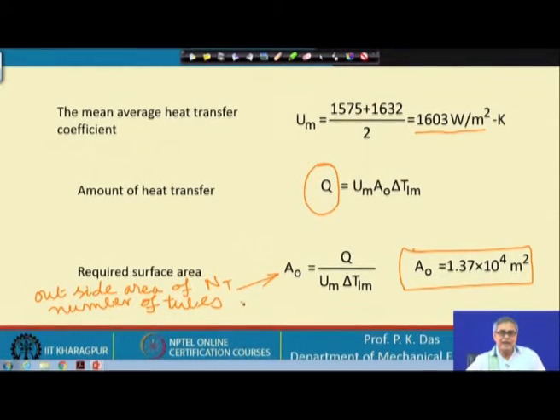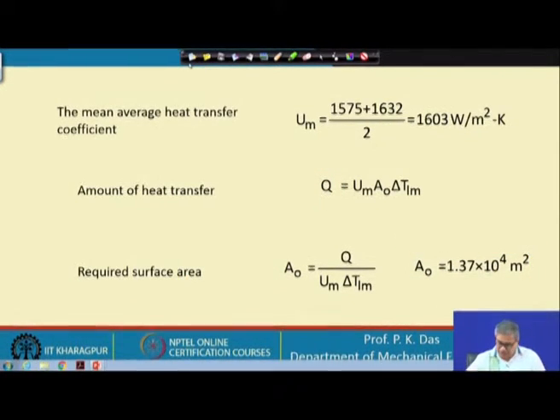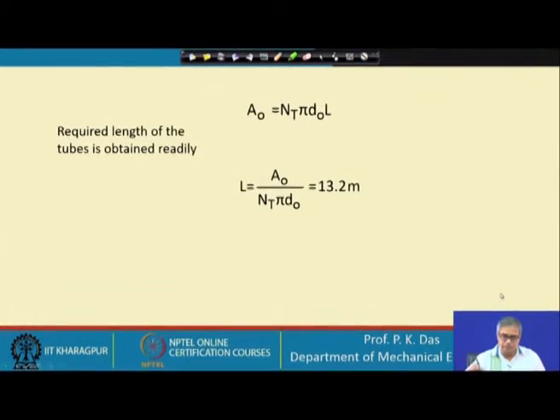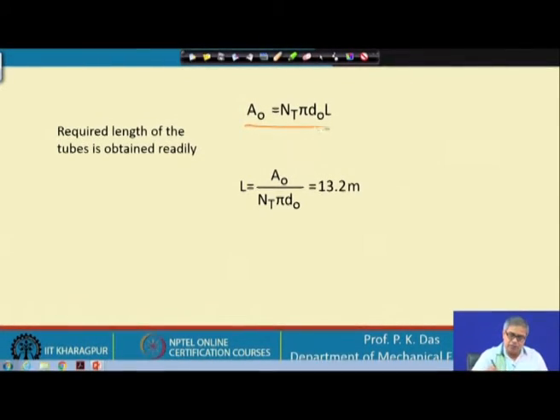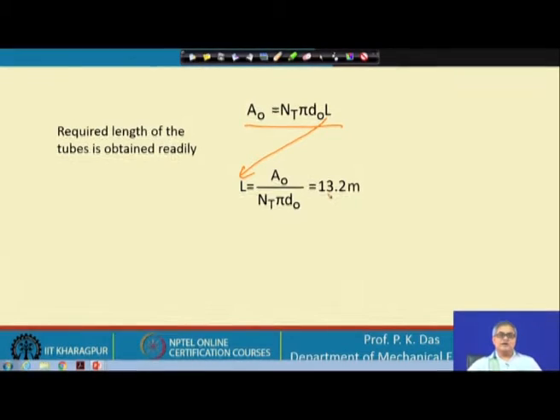From the inlet and outlet overall heat transfer coefficients of 1575 and 1632 W/m²K, we calculate the average overall HTC. The total heat transfer Q is known from earlier calculations. With Q, average U, and log mean temperature difference all known, the only unknown is A_o — the outside tube area. We then use A_o = N_t × π × d_o × L to find the tube length: L = 13.2 meters. This is the required length of each tube to achieve the desired condensation in this surface condenser.